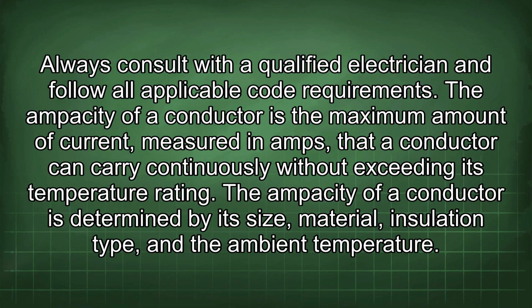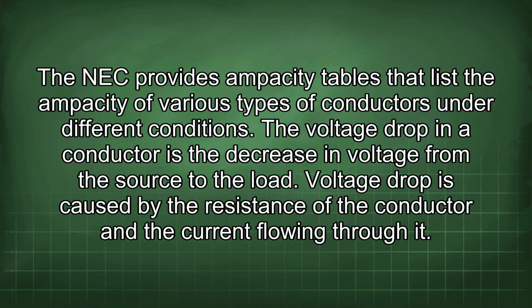The ampacity of a conductor is the maximum amount of current, measured in amps, that a conductor can carry continuously without exceeding its temperature rating. The ampacity of a conductor is determined by its size, material, insulation type, and the ambient temperature. The NEC provides ampacity tables that list the ampacity of various types of conductors under different conditions.